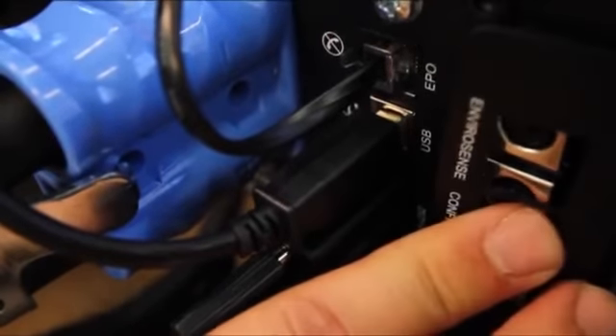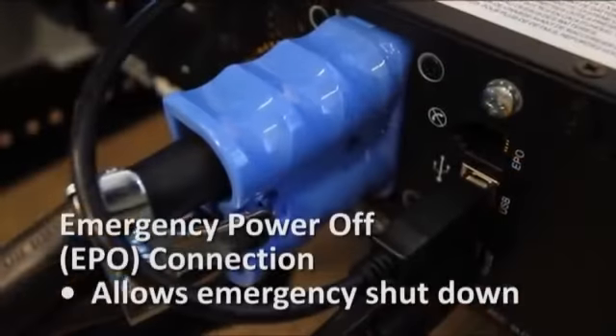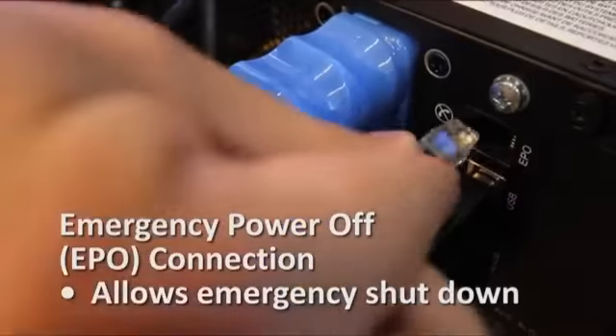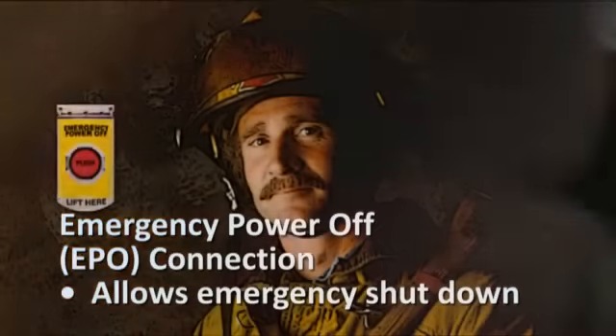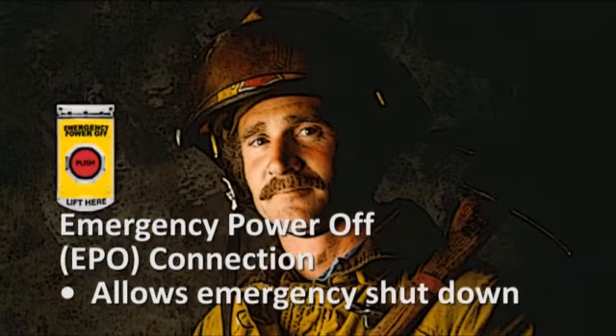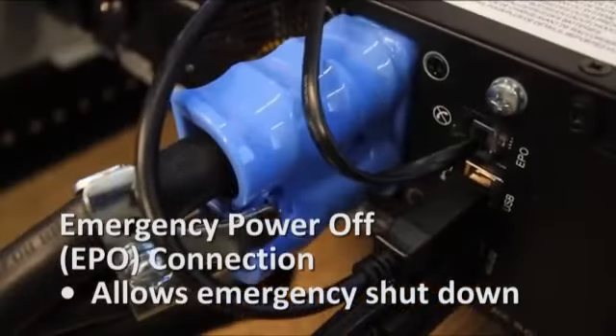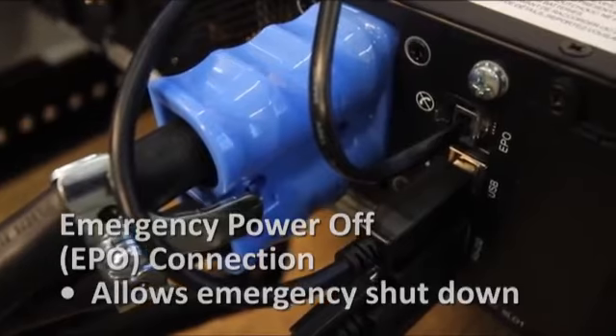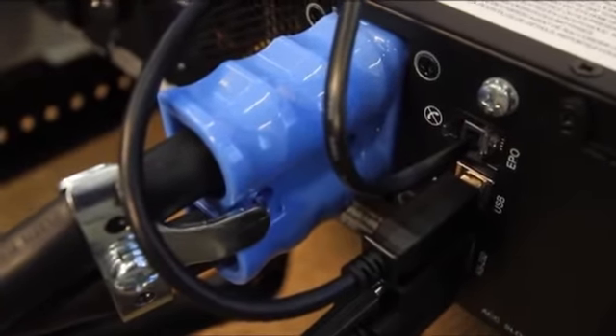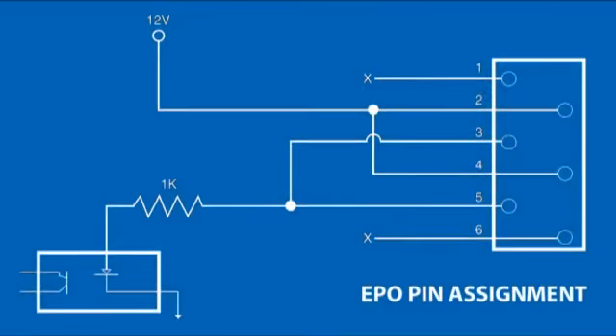This optional feature is only for those applications that require connection to a facility's EPO circuit. When UPSs are connected to this circuit, it enables firefighters or first responders to remotely shut down the inverters and inhibit transfer to internal bypass. Using the included cable, connect the UPS's EPO port to a user-supplied, normally closed or open switch. Refer to your owner's manual for additional information if you use this option.